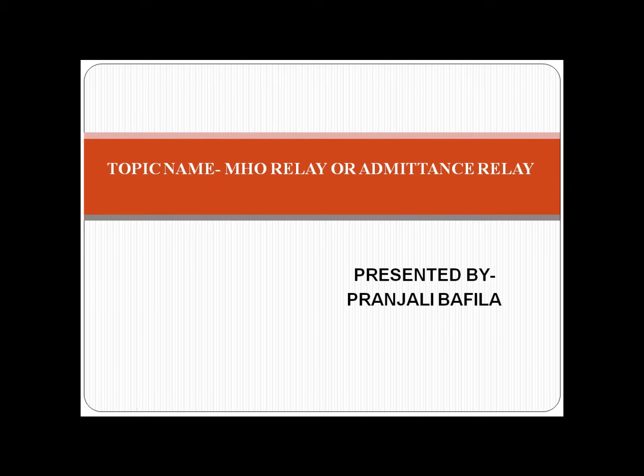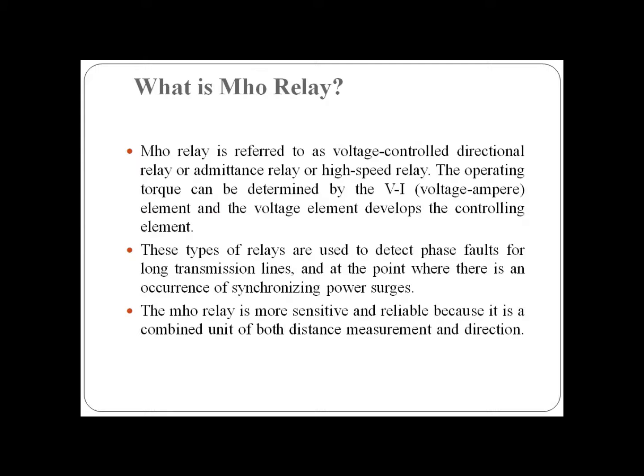Hello students, your next topic is Mho relay or admittance relay. Mho relay is referred to as a voltage-controlled directional relay or admittance relay. This relay is also known as the admittance relay or high-speed relay. In this relay, the operating torque can be determined by the VI element, and the voltage element develops the controlling element.